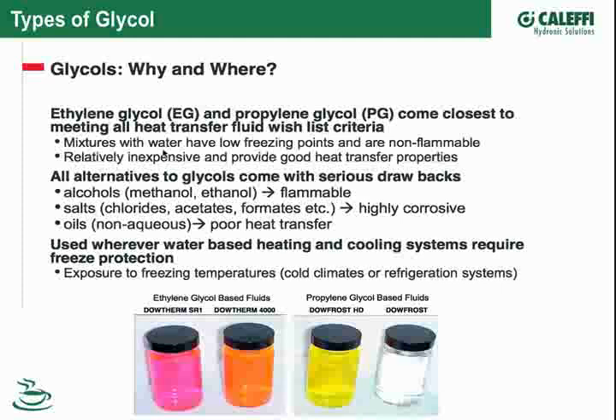Absolutely. Think refrigeration, like ice skating rinks and the like, will tend to go with ethylene glycol-based products because at low temperature, the viscosity of propylene glycol is quite a bit higher than ethylene, and that affects your heat transfer and your pumping horsepower. So ethylene glycol is still a viable option. It comes down to making that choice: performance versus safety or environmental impact.